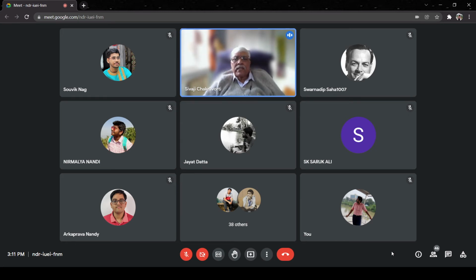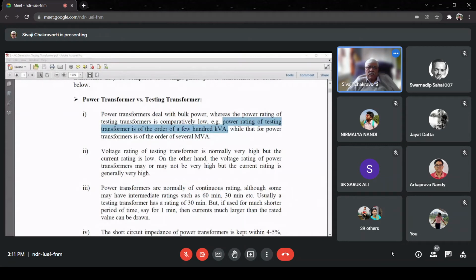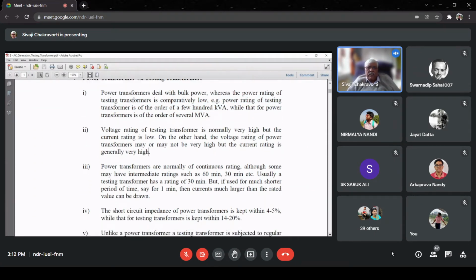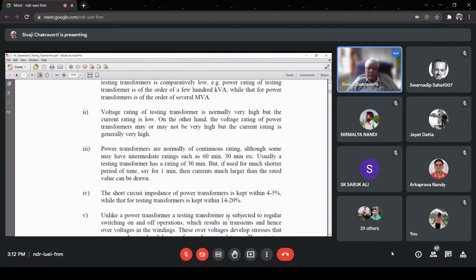So let me go back to our basic discussion point again. So power rating is one major difference between a power transformer and a testing transformer. Then voltage rating, that is an important issue. See, if our system voltage is 132 kV, the test voltage will not be 132 kV. It has to be higher because we always have to test whether the insulation is able to withstand overvoltages. That is the important part. So the voltage rating of a testing transformer is normally very high, but the current rating is generally low. On the other hand, the voltage rating of the power transformer may or may not be very high. It could be 400 kV also. But most importantly, the current rating will also be very high because they are supposed to carry power of the order of megawatts.